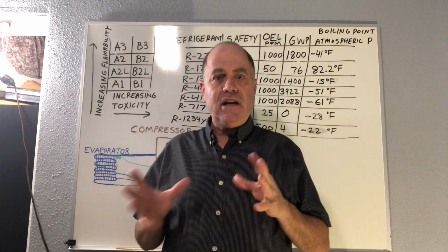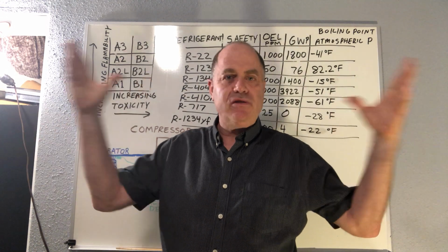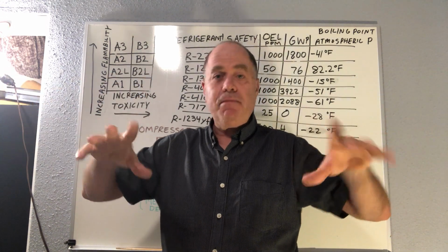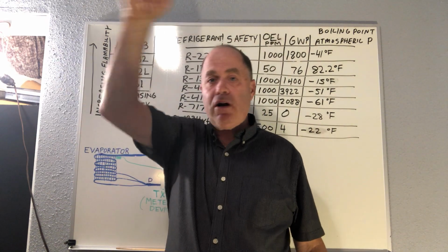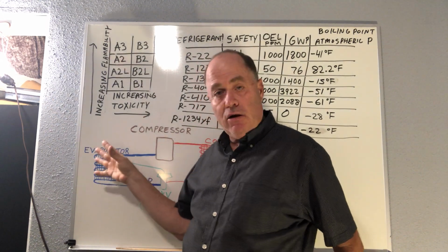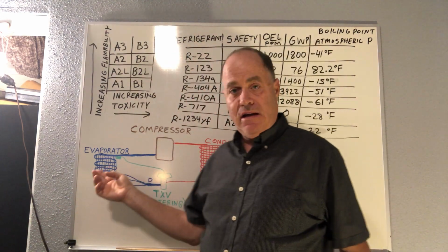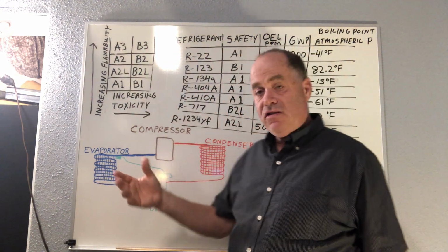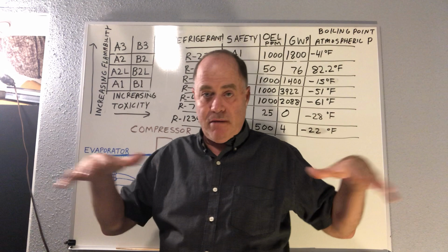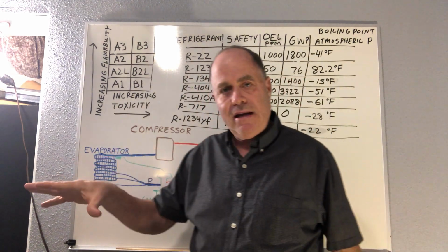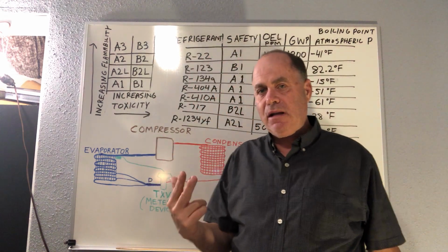We tend to have these chillers they make chilled water, where you have the giant chiller with 1,000 or more pounds of refrigerant in, not an occupied space, but a machine room. And then we chill water, and then we pump that water through coils, kind of like this, and blow air over it to cool. And a lot of times we might have 50 or more of these chilled water coils serving certain areas, right? And a lot of different areas have different temperature requirements and whatnot, so we control that zone individually.